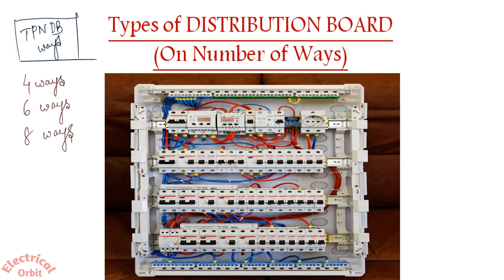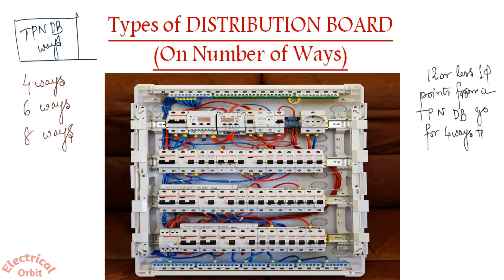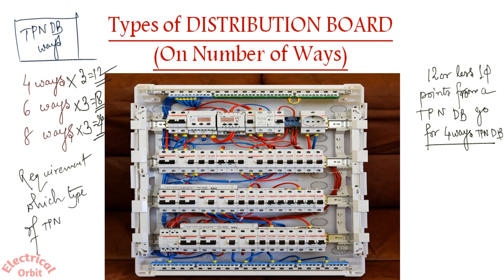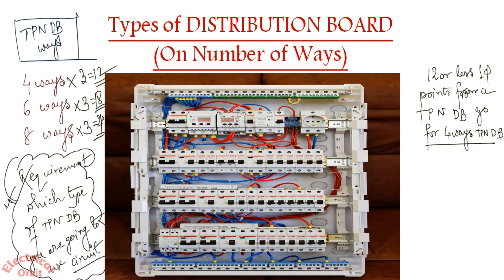There is a simple rule for TPN DB ways: the number of ways is multiplied by three to get the number of single-phase outputs. From a four-way TPN DB you get 12 single-phase outputs; from a six-way you get 18 outputs; and from an eight-way you get 24 single-phase outputs. You choose the TPN DB type based on your requirements.